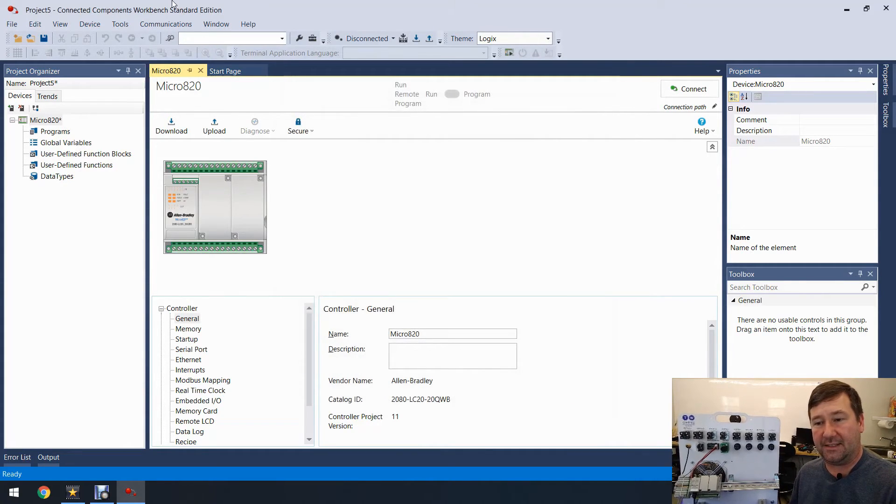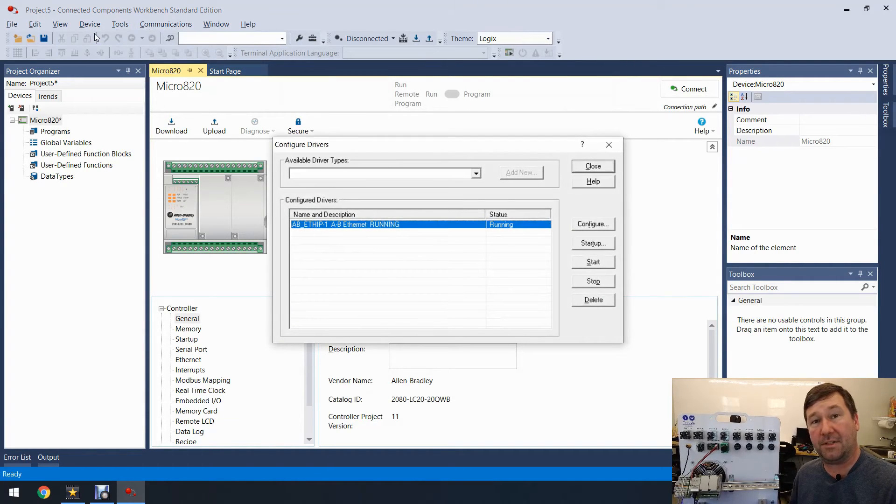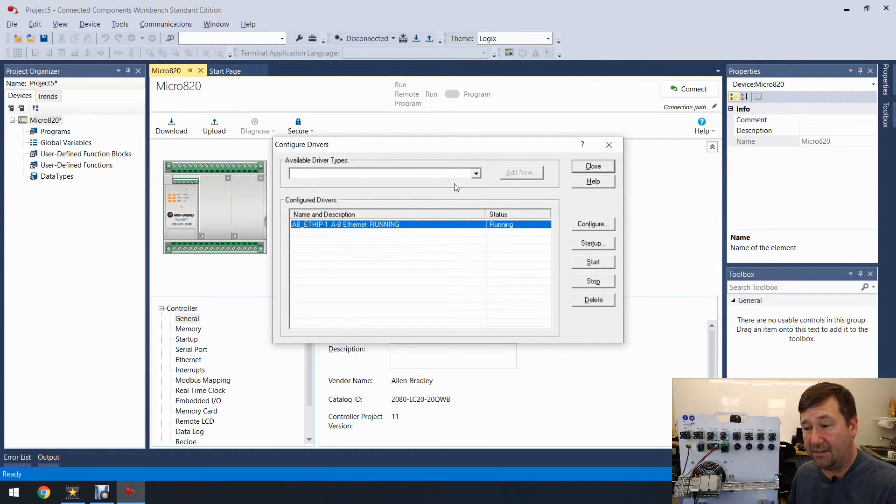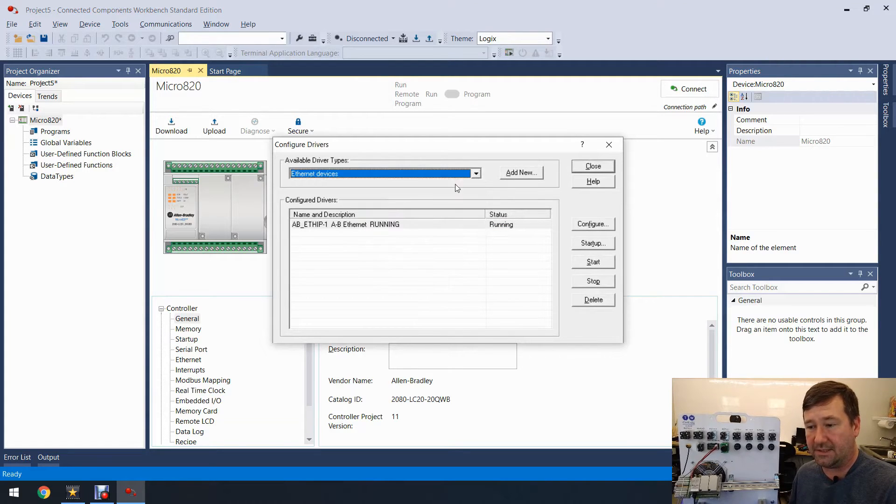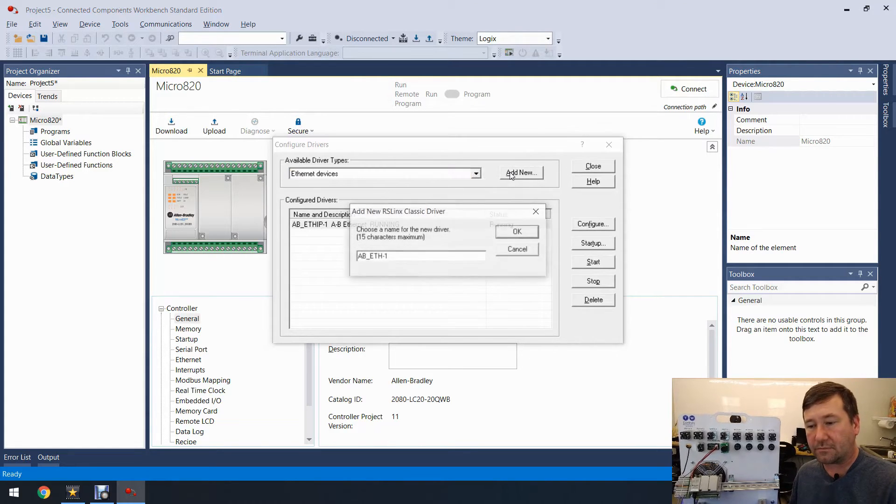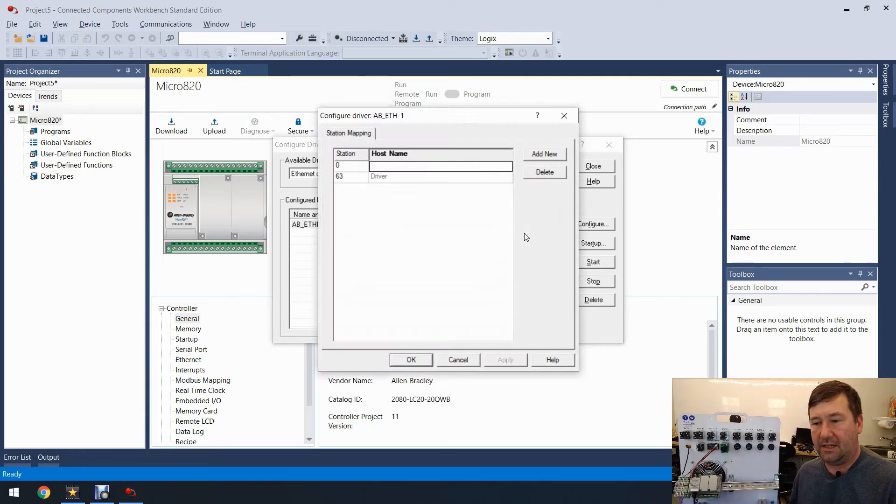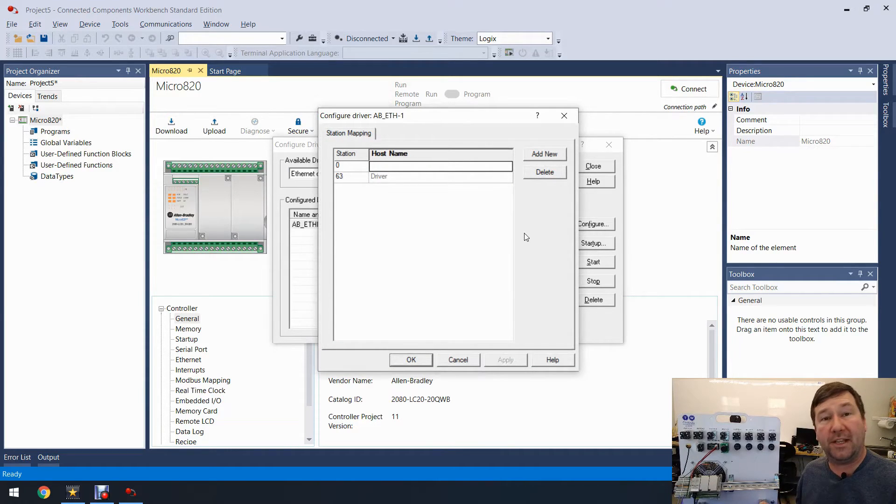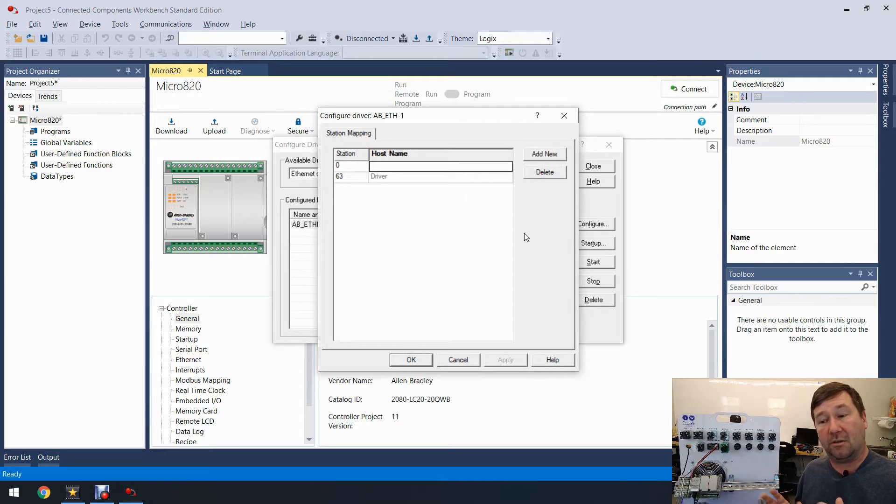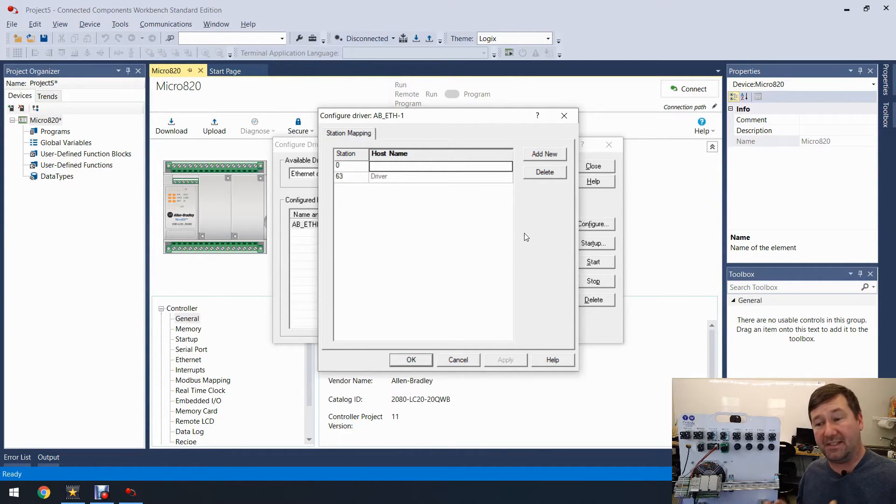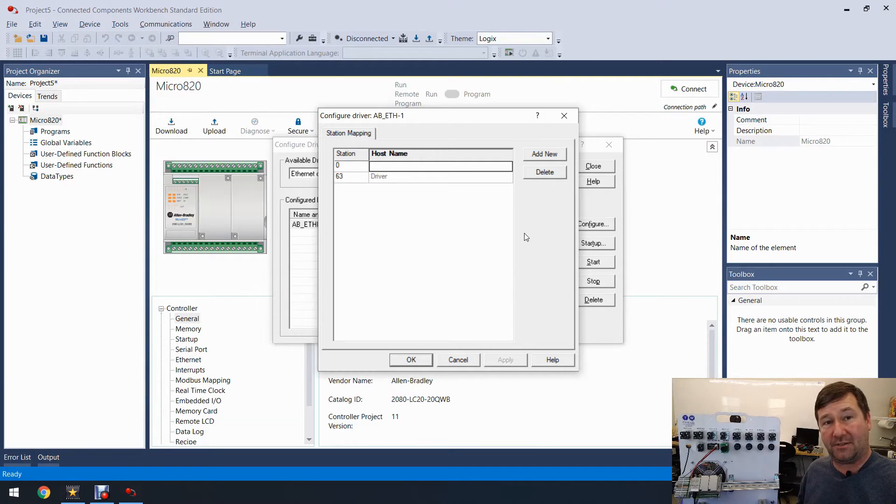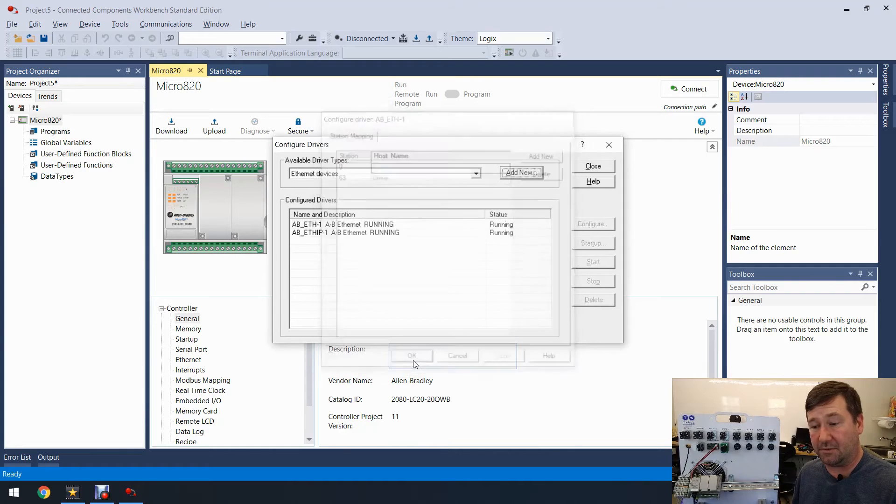So let's back out of this and let's go back to Communications, Configure Drivers and let's add the Ethernet Devices driver. So Ethernet Devices, Add New. On the last one it just asked which adapter you wanted to use and it went and listened for the packets. Well this time it is asking for this station mapping and this station mapping is the IP addresses that it should look for PLCs at.